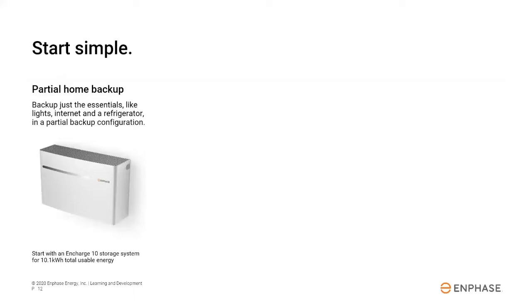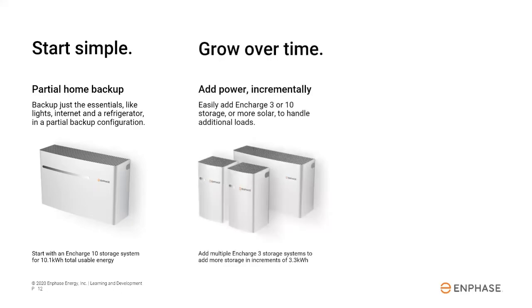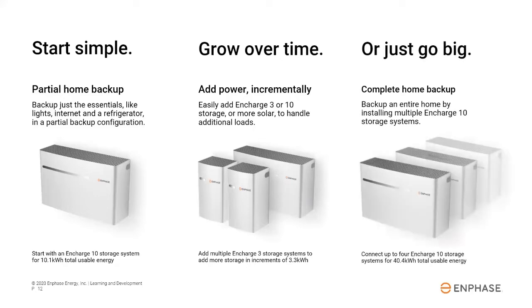Enphase Storage is designed to be modular, and it's suitable for homes of all sizes. There are 2 battery capacities available, a 3 kilowatt hour and 10 kilowatt hour, and they can be easily combined to tailor the system size for the specific needs of the owner. A home which requires backup of only essential loads like refrigeration, lighting, and electronics might just need 1 Encharge 10. A homeowner may want to add more storage in the future as their family grows and their energy needs change. Just add more Encharge units to the existing system. A large home with air conditioning and a well pump may require backup of all loads and could use 4 Encharge 10s. No matter what the requirements, the Enphase storage system can be customized to meet their needs.